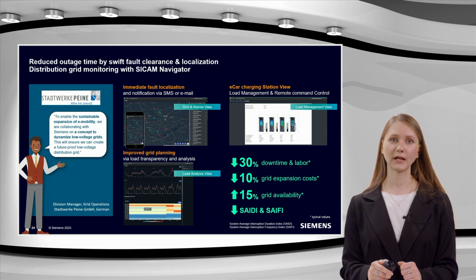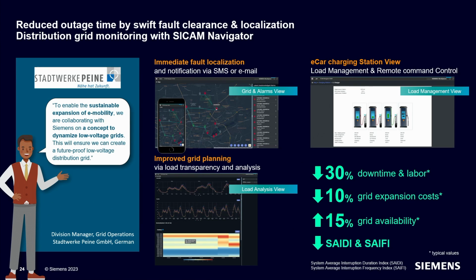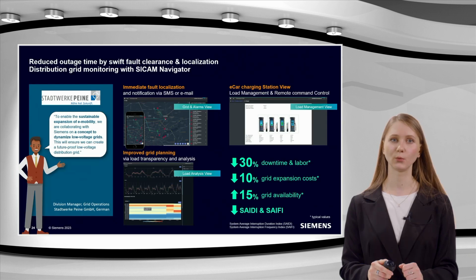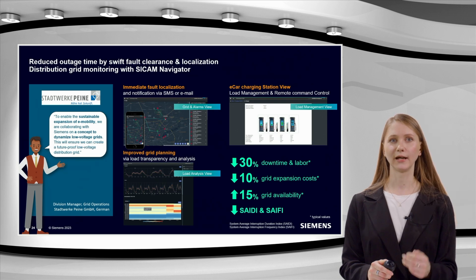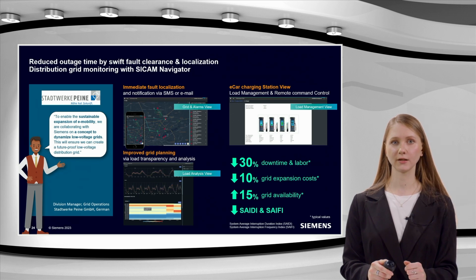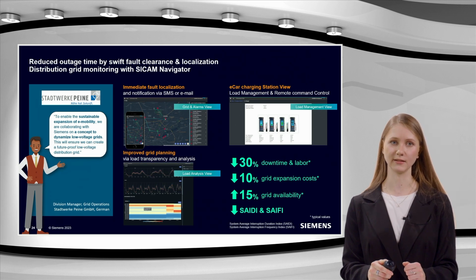The application enables power grid operators to immediately detect and localize faults in cable network-based transformer stations. We are collecting all necessary measurements and alarms and send them to the application, all without traveling to the substation as you have done in the past. You can keep an eye on all your substations and critical assets while sitting at home. It also helps improve grid planning via load transparency and analysis.